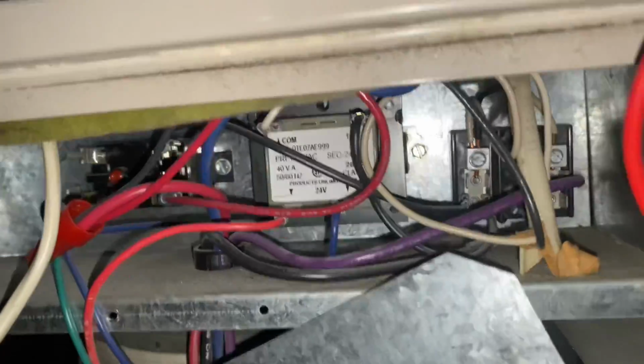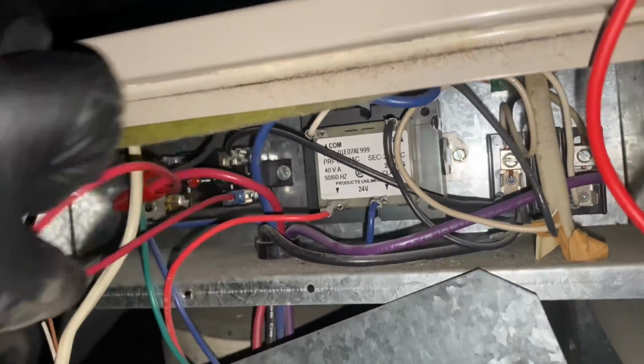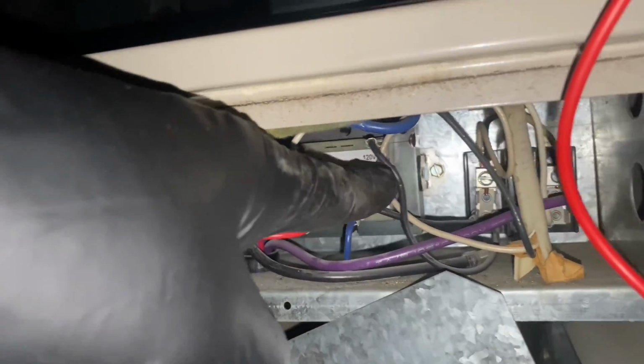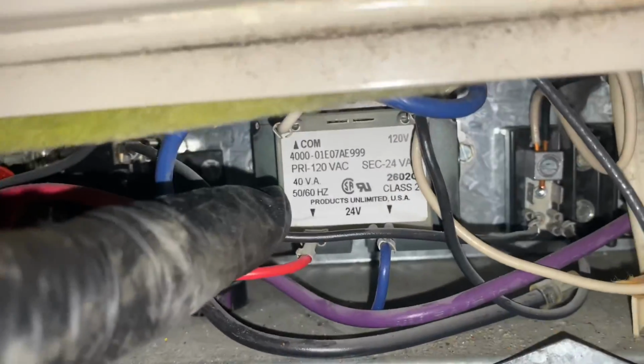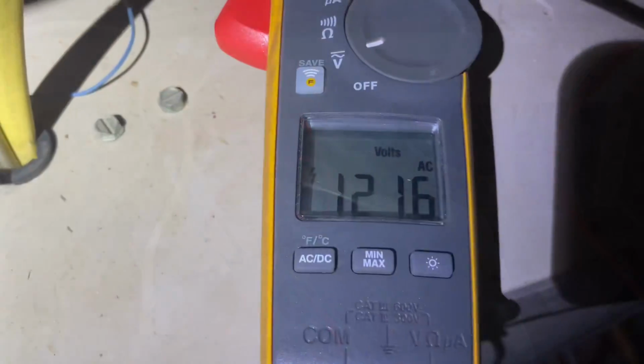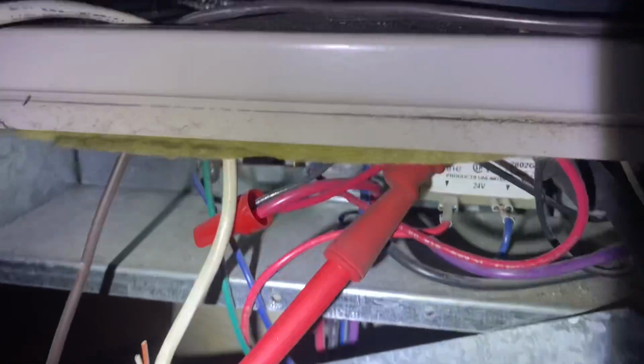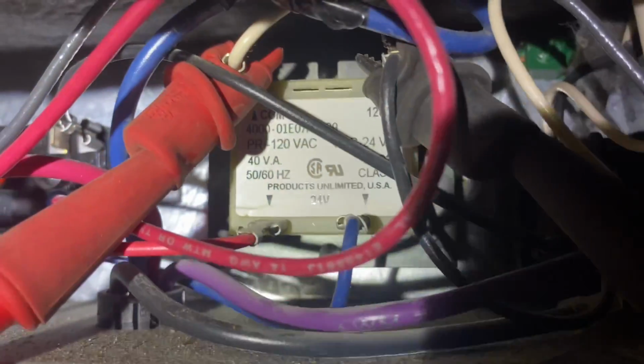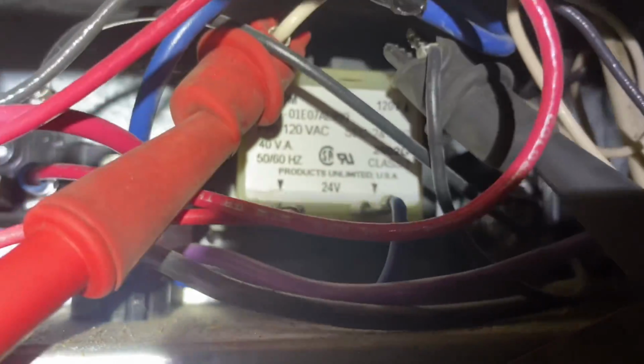So now I'm going to go to that transformer right there. I'm going to go between 120 and common, see what kind of voltage we have there. So I have 120 volts between common right there. See common? And 120 volts. So I have line voltage going in.